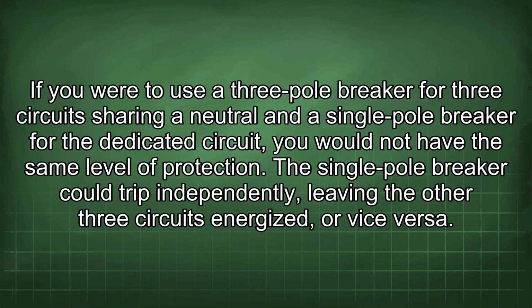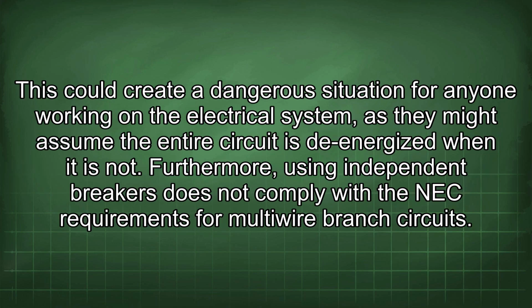If you were to use a 3-pole breaker for 3 circuits sharing a neutral and a single-pole breaker for the dedicated circuit, you would not have the same level of protection. The single-pole breaker could trip independently, leaving the other 3 circuits energized, or vice versa. This could create a dangerous situation for anyone working on the electrical system, as they might assume the entire circuit is de-energized when it is not.